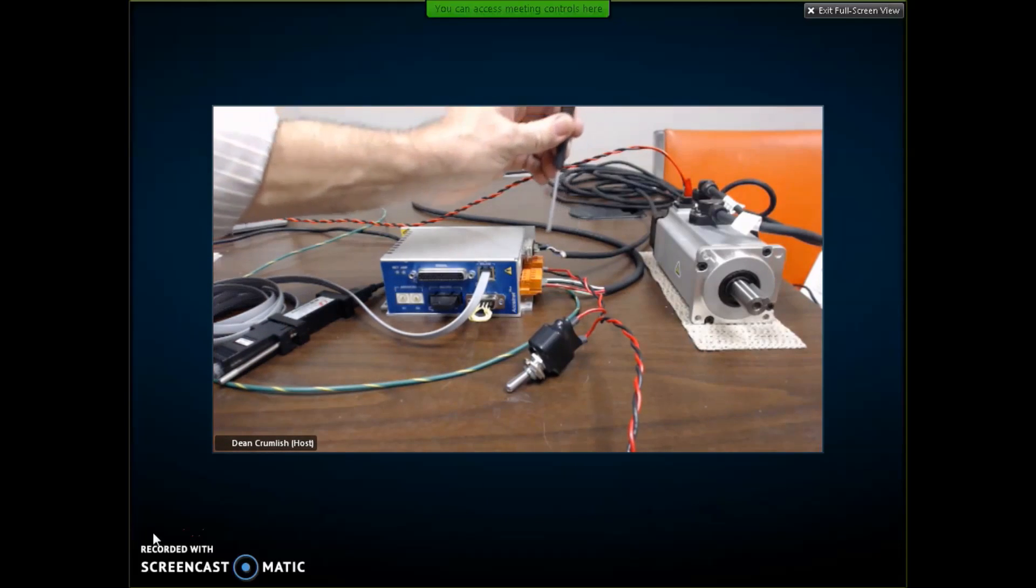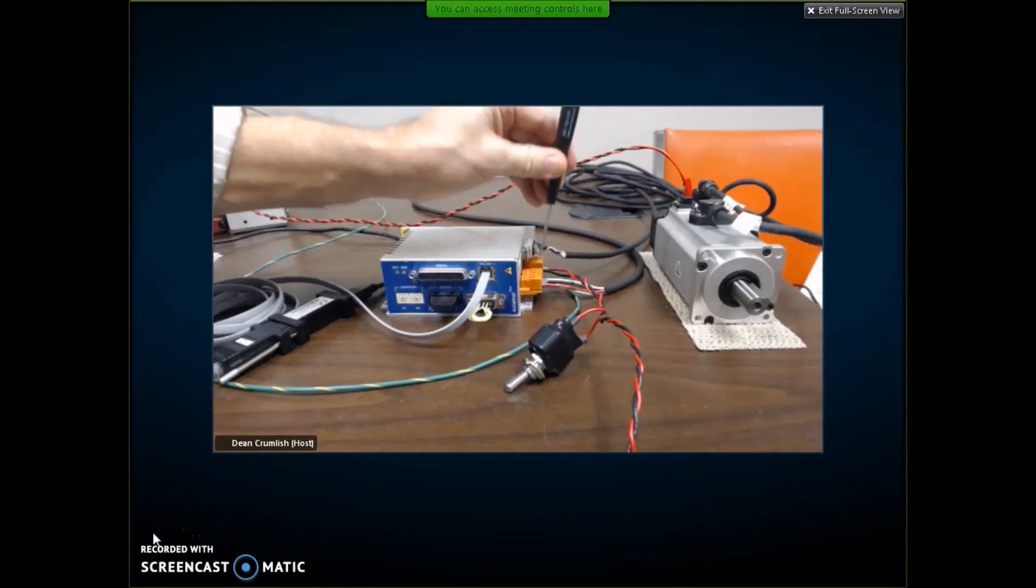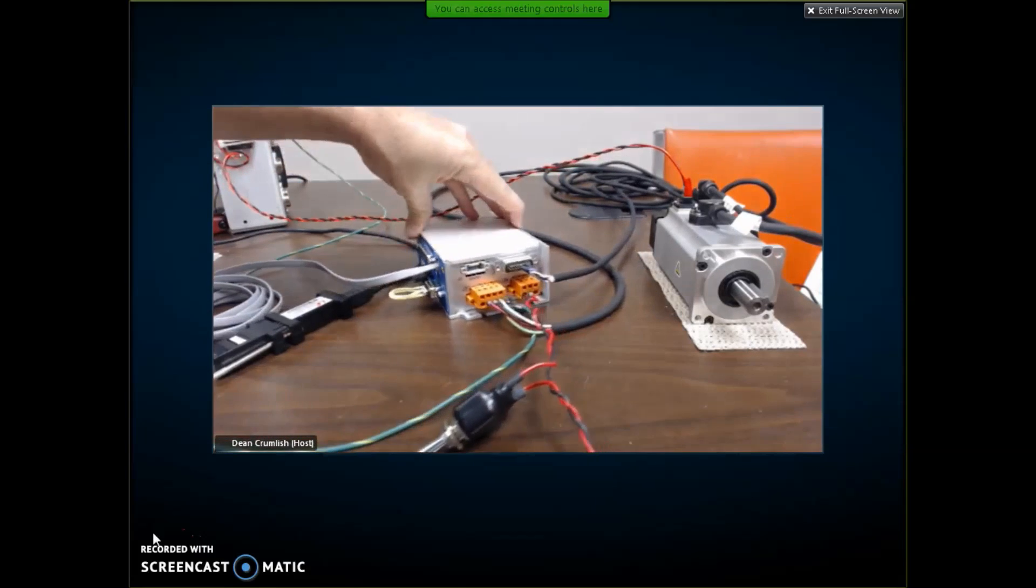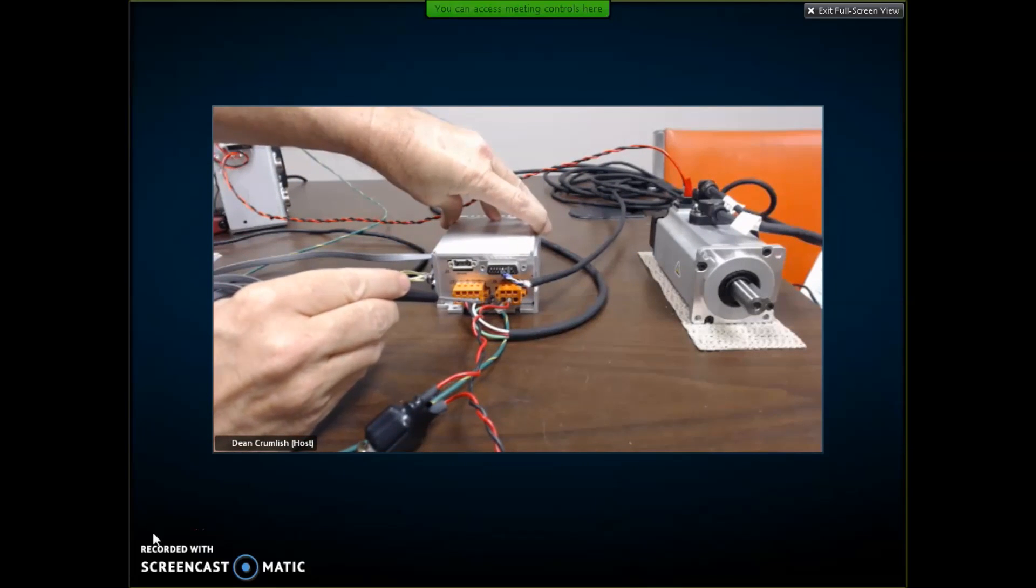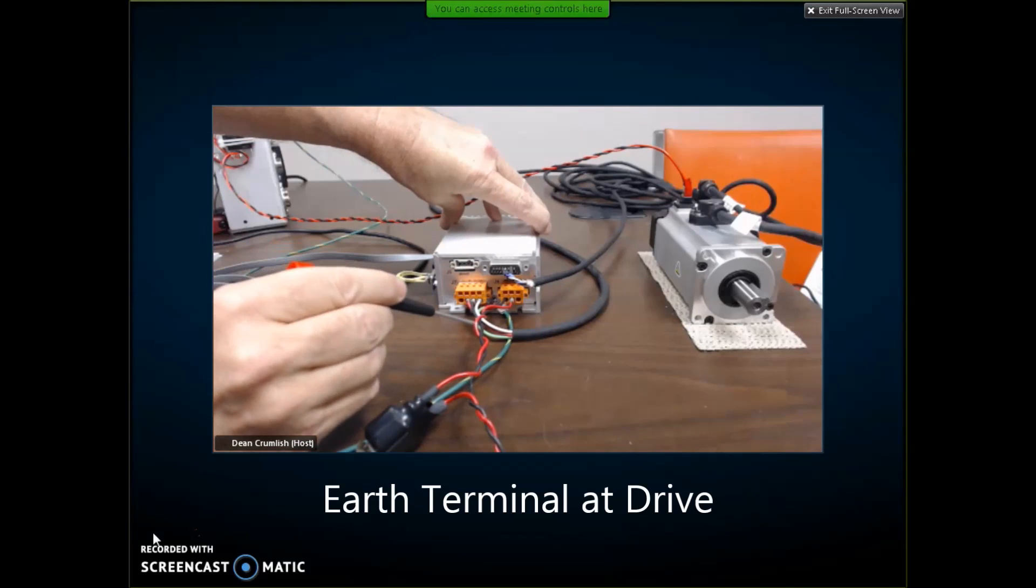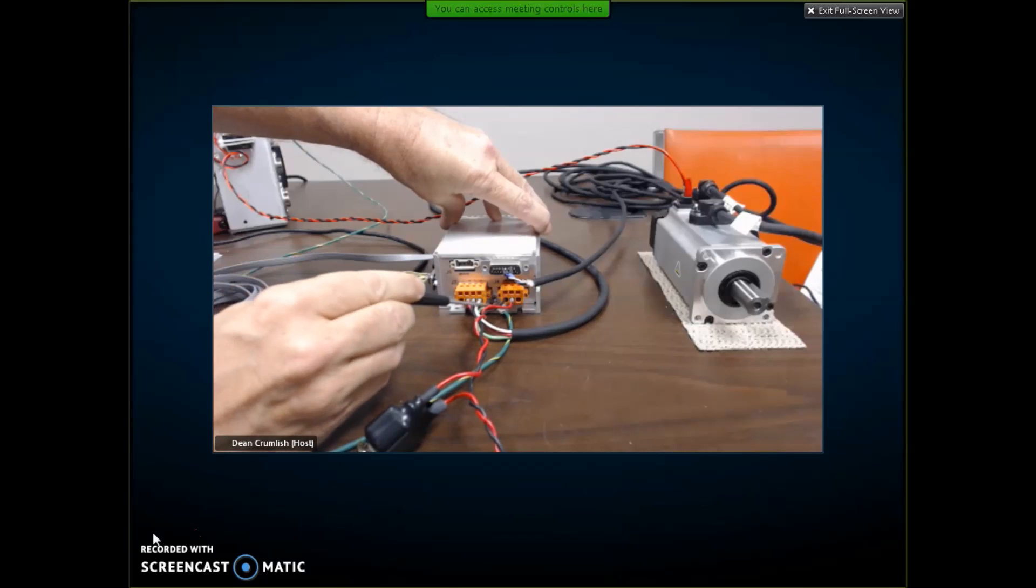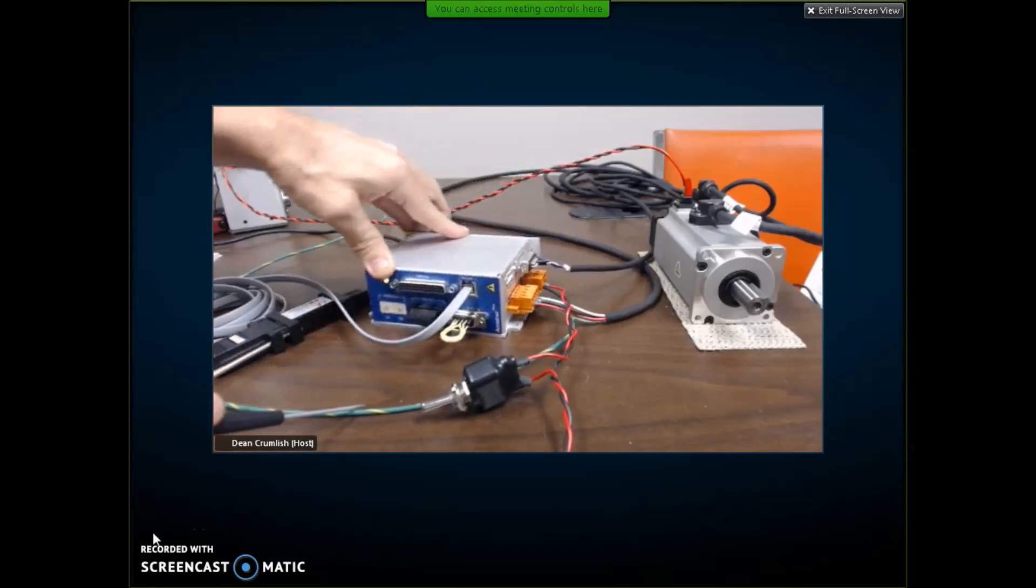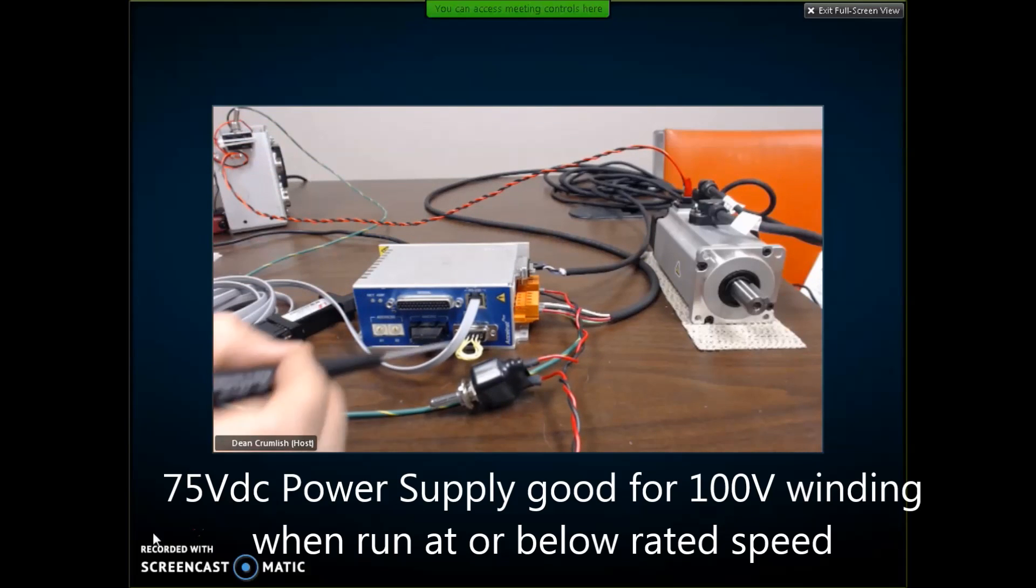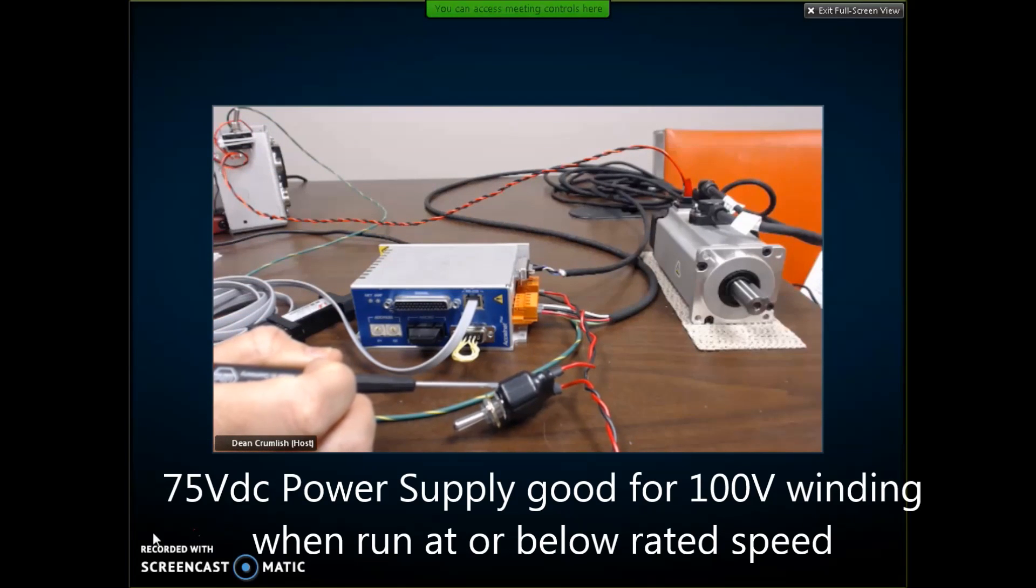I've got Earth connected to the drive. There's a convenient location, the screw and nut already available for Earth. I've connected the motor frame to the same Earth. This green and yellow wire runs back to the Earth connection. I'm running off a 75-volt power supply today.